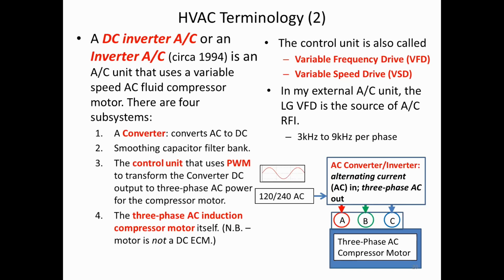And what it consists of is a converter that converts AC to DC, a smoothing capacitive filter bank, a control unit that uses, guess what, pulse width modulation to convert the DC output to 3-phase AC power for the compressor motor. And then finally, most AC units have 3-phase AC induction compressor motors. They don't have DC motors, but the damage is being done by the inverter, which uses pulse width modulation. By giving you 3-phase AC, the pulse width modulator can vary the amplitude of the 3-phase AC, which in turn varies the speed of the compressor motor.